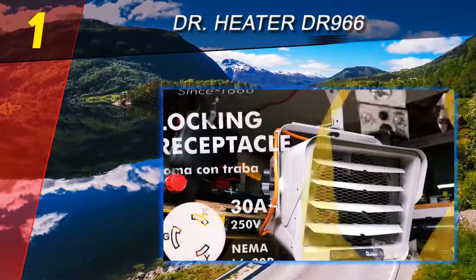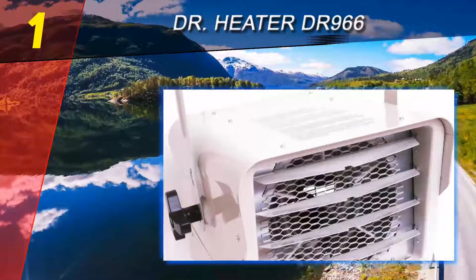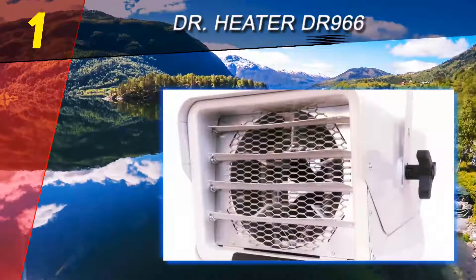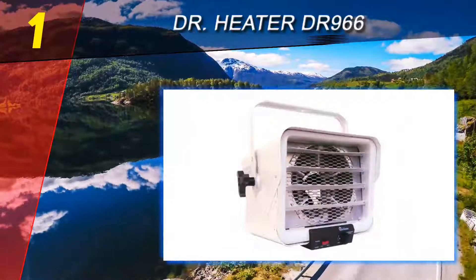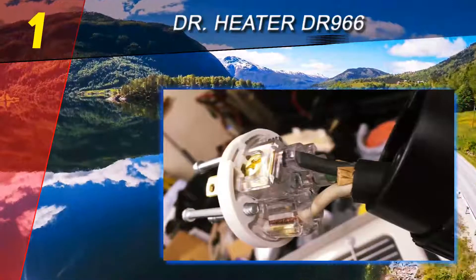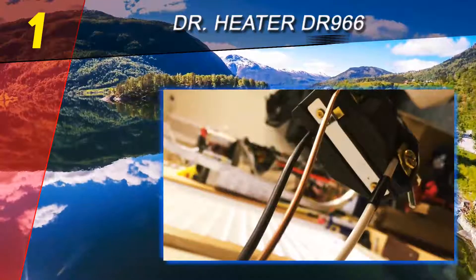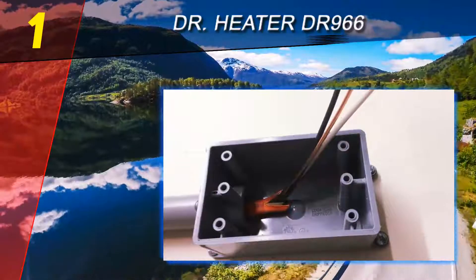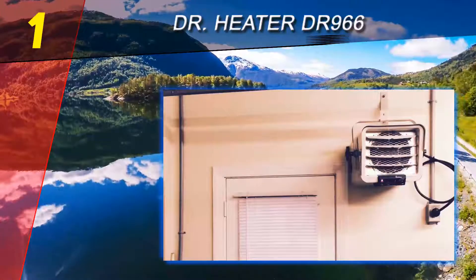You might be able to get away with a 10/3 wire on a 30-amp breaker, but this isn't specified in the provided pamphlet, which could result in voiding your warranty. As for room size, you may have trouble heating large rooms, and this issue is made worse if you use the low setting, which is about 3,000 watts. Heat at the 6,000-watt level is fine, but running it at anything less than the highest setting won't have a noticeable effect — especially in climates that stay frigid for most of the day in winter.